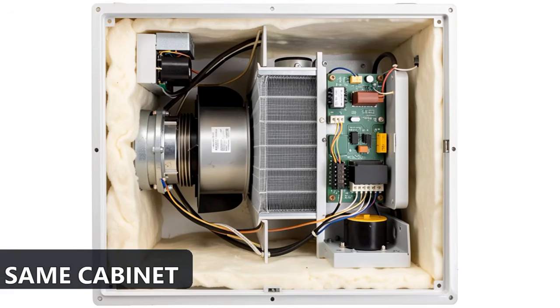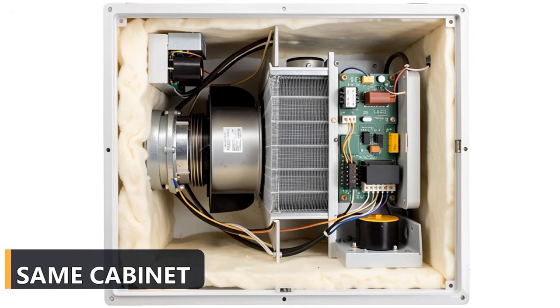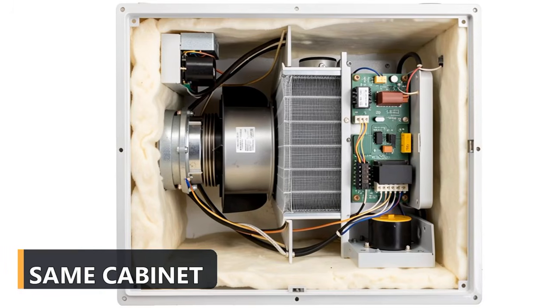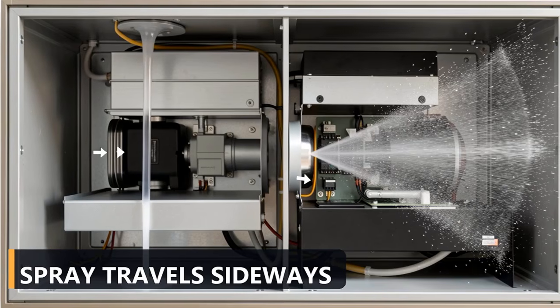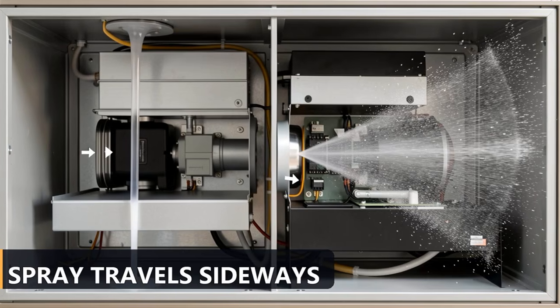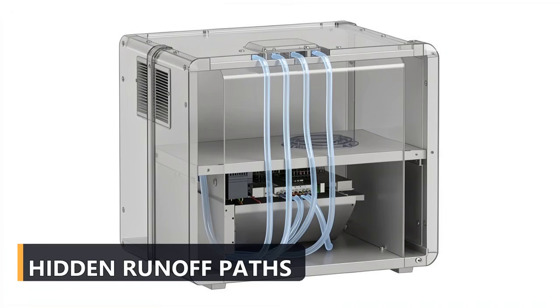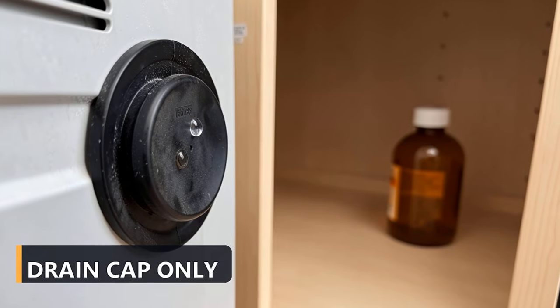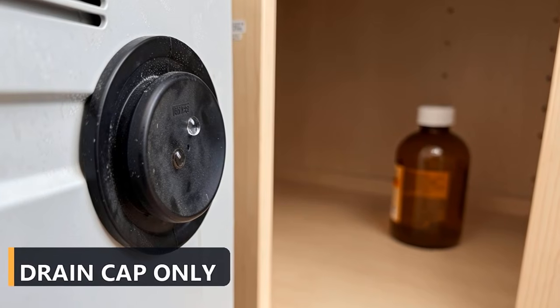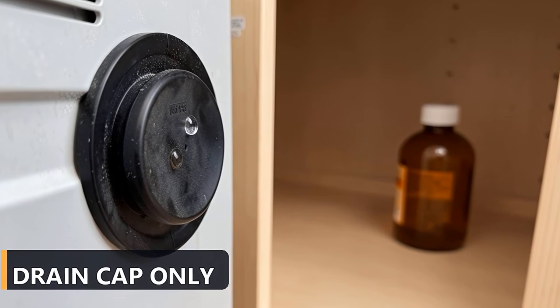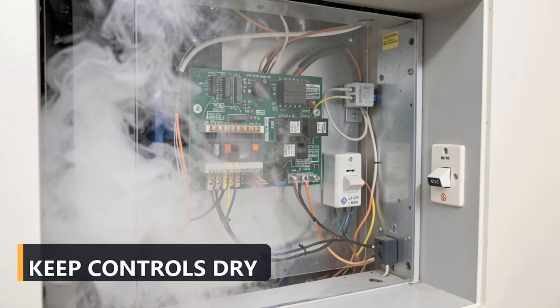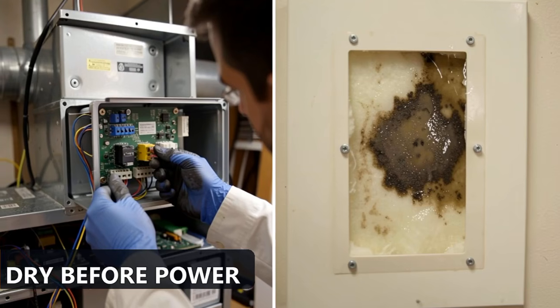Number 4. The most expensive parts may be only inches from the satisfying foam. Look beyond the coil. Depending on the air handler, there may be a blower motor, circuit board, transformer, sensors, wire terminals, insulation, and safety switches inside the same cabinet. Gravity pulls liquid down, but a spray creates droplets that travel sideways. Foam can expand into seams. Runoff can follow wiring or collect beneath components where you cannot see it.